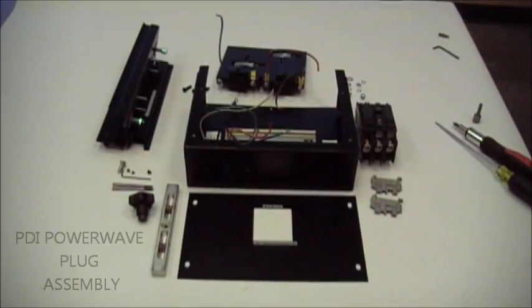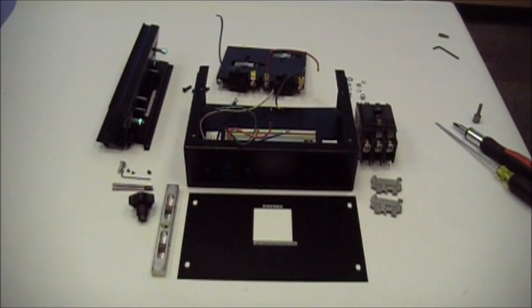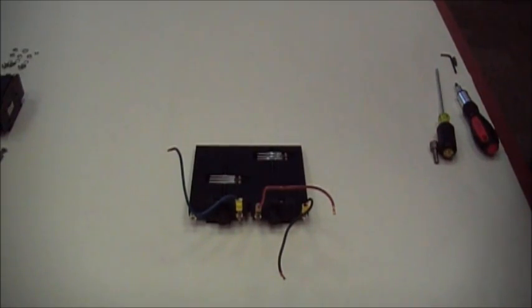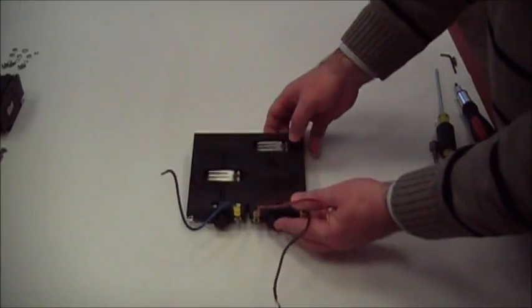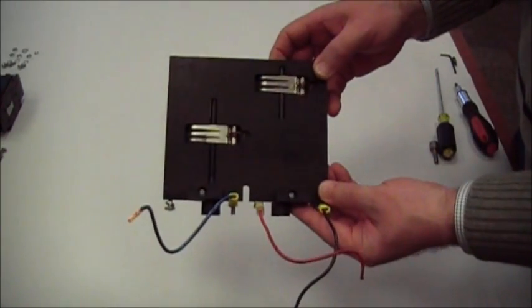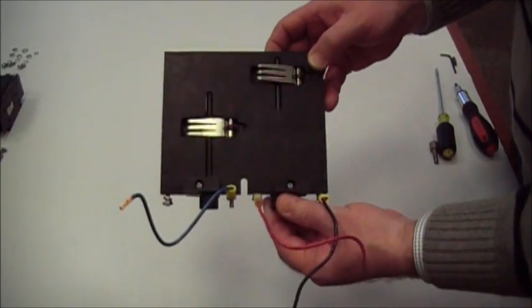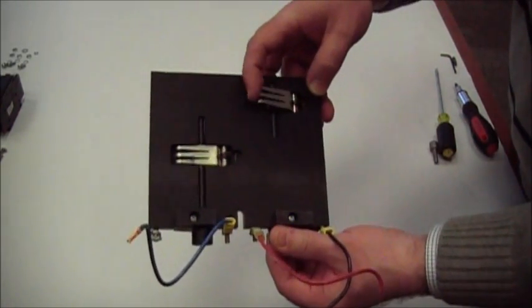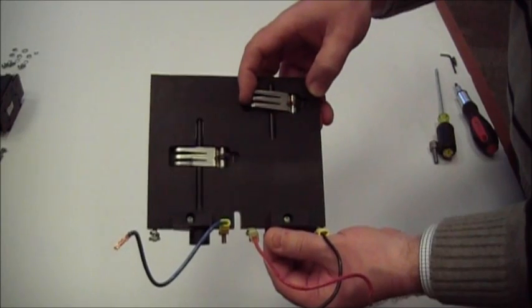Next, we'll assemble the Power Wave bus plug. And to do that, we'll again start with the paddle and work our way into the enclosure. We won't go into the paddle assembly, but we will show you the paddle that goes into the busway housing. So the paddle requires a mechanism to actuate the fingers, which will press against the busway when it's inserted into the housing.